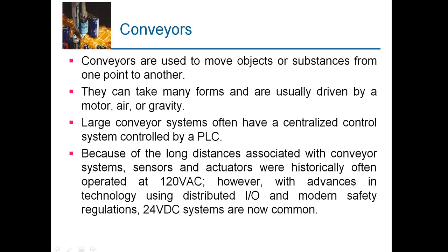Large conveyor systems often have a centralized control system called PLC — Programmable Logic Control. Because of the long distances associated with conveyor systems, sensors and actuators were historically operated at 120VAC. However, with advancing technology using distributed I/O and modern safety standards, 24 volt DC systems are now used, so there is no shock or hazard. These are controlled by the programmable logic controller. A human machine interface is also present, and there will be an emergency stop to halt the conveyor.